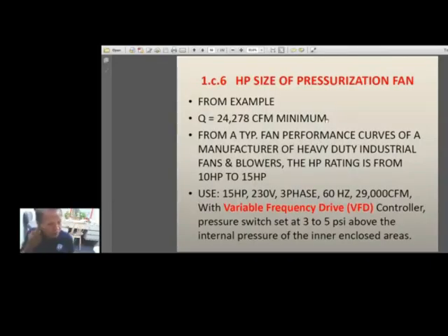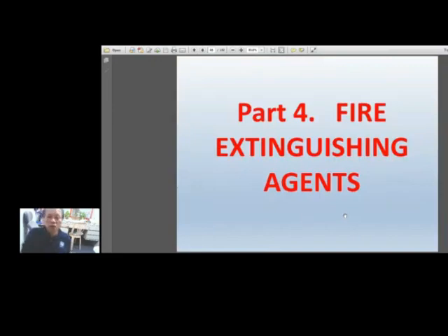and here is a way to size it up. I already indicated for a, not a 22, 11-story building. The calculated fan capacity is 24,278 CFM, and the fan was selected at 29,000 cubic feet per minute, driven by a 15 horsepower motor and controlled by a variable frequency drive. Okay, so the pressurization fan maintains something like 3 to 5 psi pressure, a little higher than the pressure inside the burning room. Okay, now we go to fire extinguishing agents.